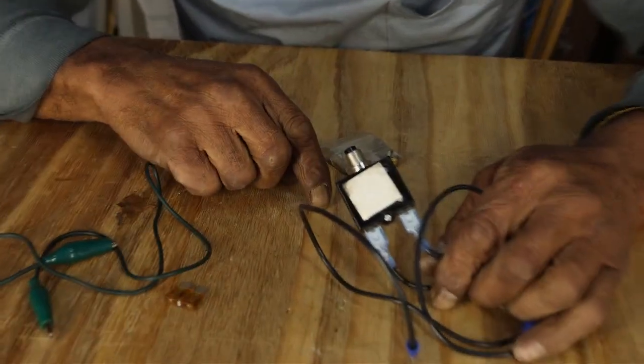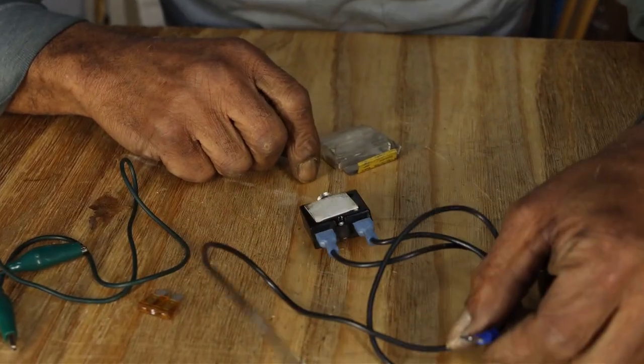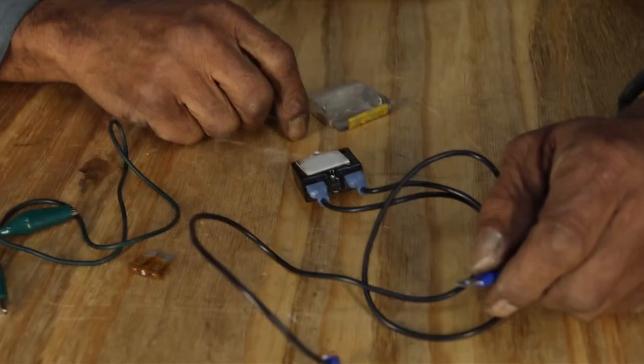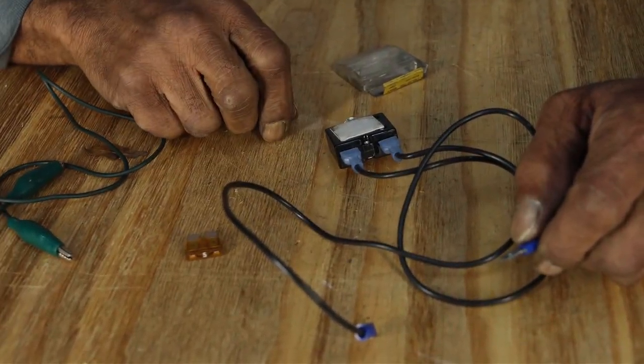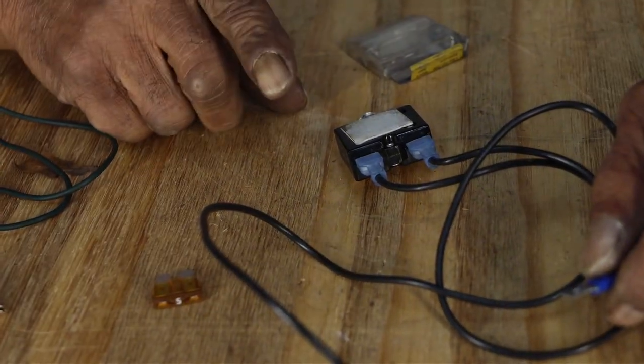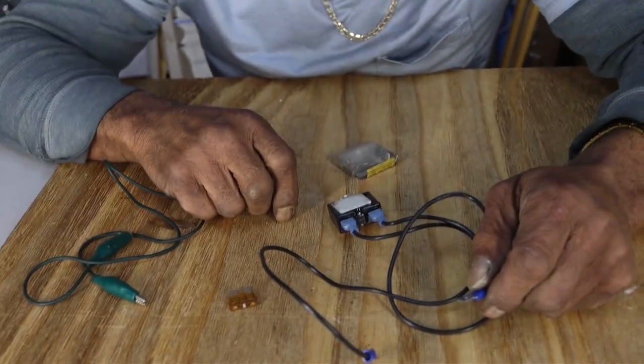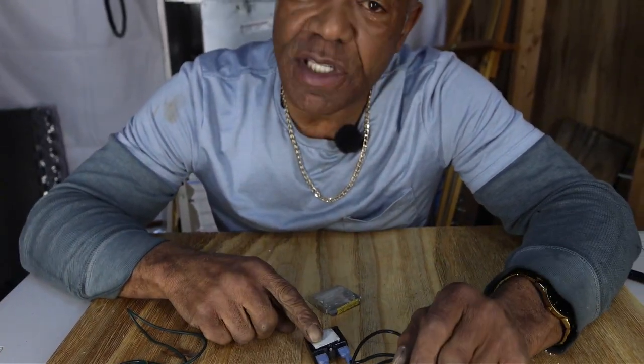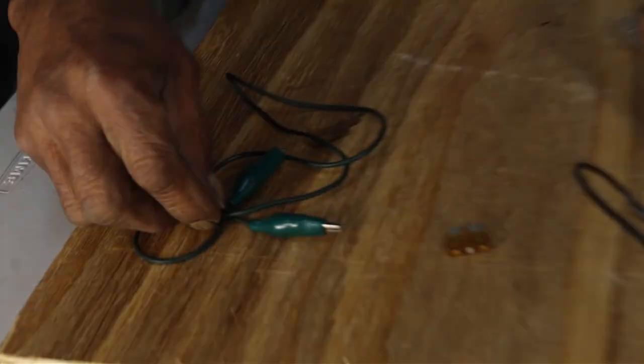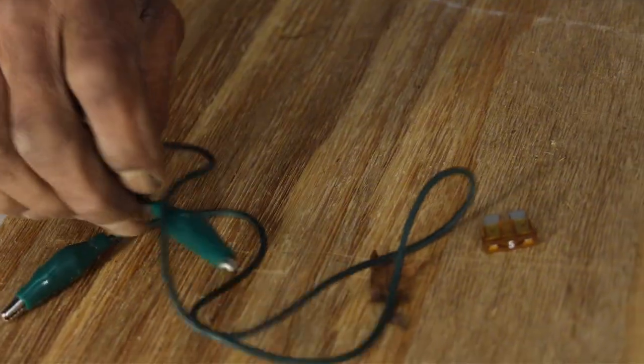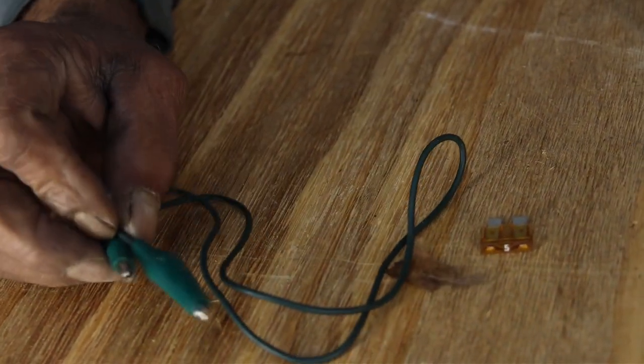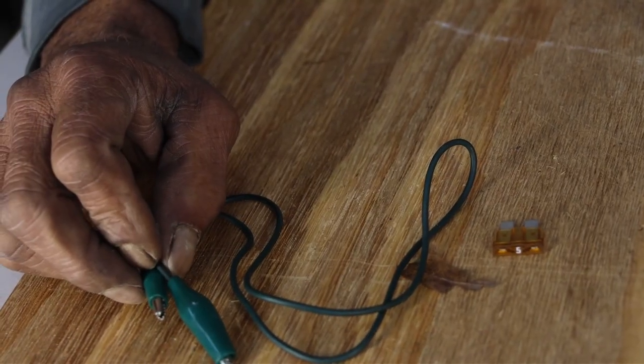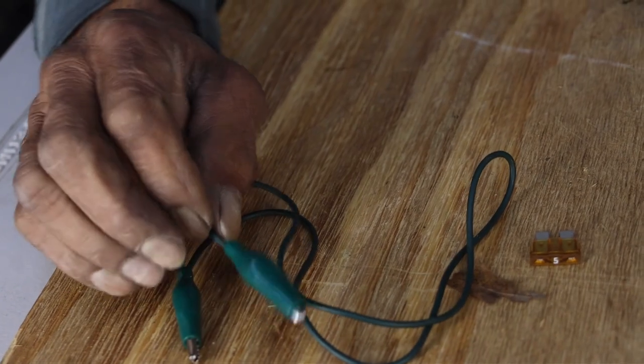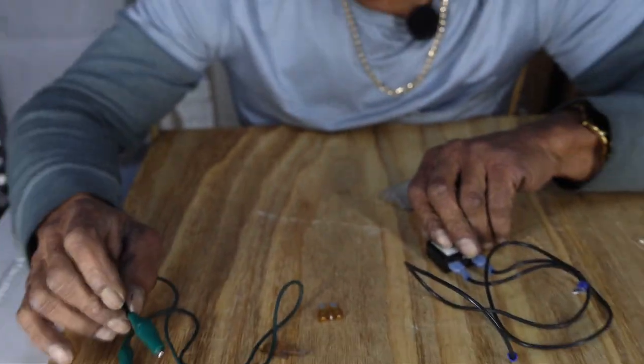Remember, this is basically a resettable fuse. It resets, so it allows me to trace, troubleshoot without continuously putting new fuses in. If there's a short in the system, every time you turn it on, it's going to blow the fuse until you find that short. By using this, I can trace the short and not have to keep replacing fuses. The alligator clamp allows me to bypass certain devices within the system, allows me to jump certain devices so that as a part of my troubleshooting, I can determine where the problem is.